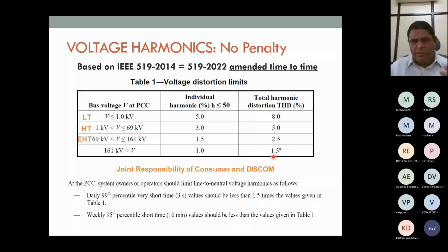So how to measure voltage harmonics? I would like to inform everyone, the current TNERC regulations do not impose penalty for violations in voltage harmonics. It doesn't mention it. So I personally feel that there will not be any penalty if there are violations. Last time in 2014, for some people, penalty was imposed for voltage harmonics also, but this time it may not be for voltage. It is categorized in three categories: for LT consumers, which is below 1 kV, 1000 volts; then for HT consumers, 1000 volts to 69 kV; then for extra high voltage consumers. These are the three categories. I don't think there are any consumers with 161 kV and very, very high voltage levels in India.